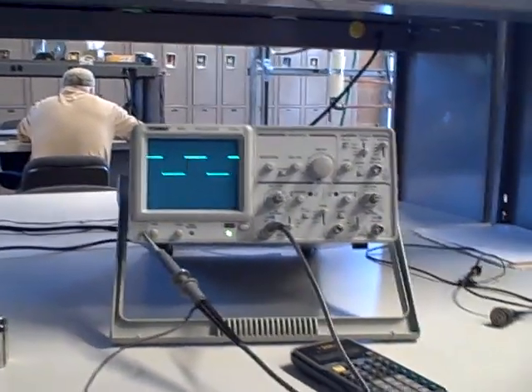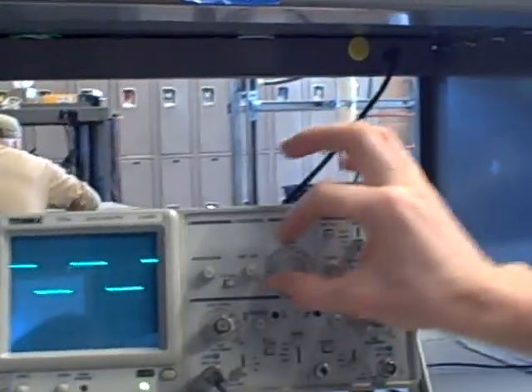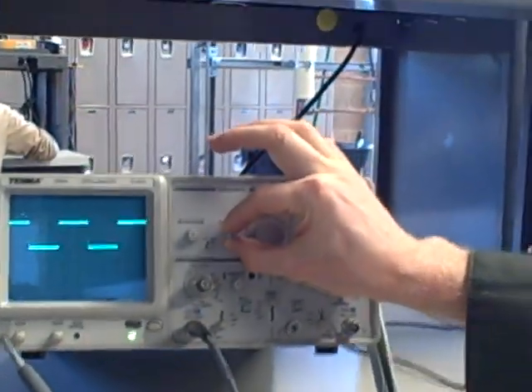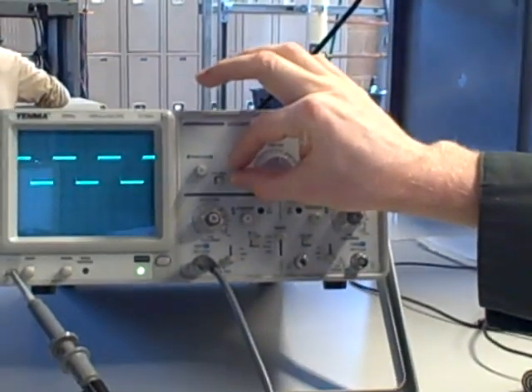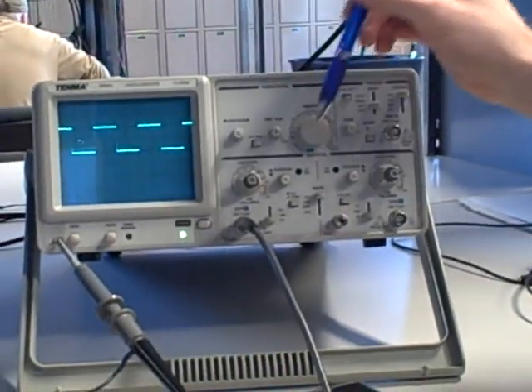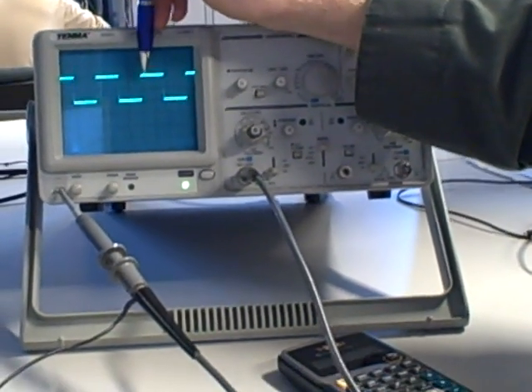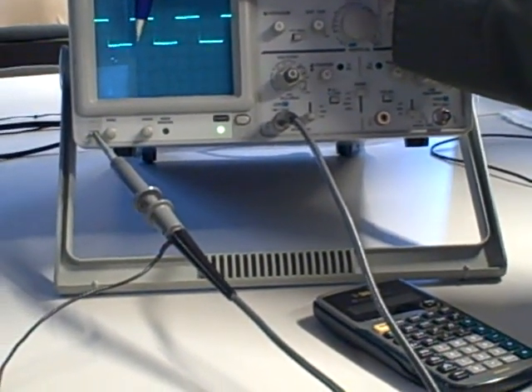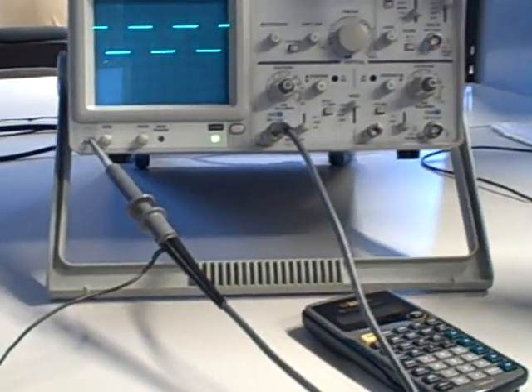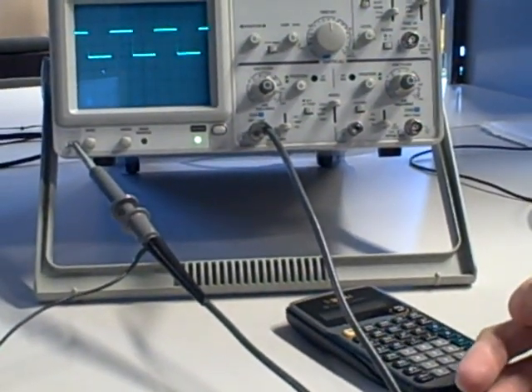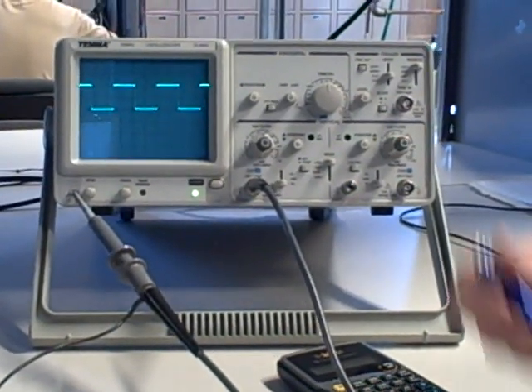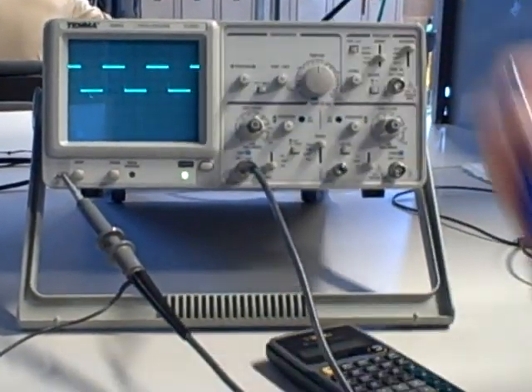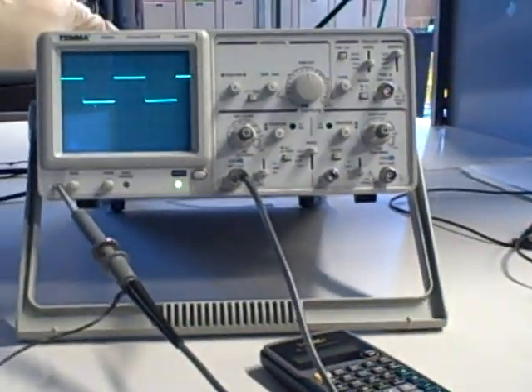In fact, I'll even prove that. I will take this sweep variable knob right here and move it off of calibration. And notice what happens. Now I can move it to any arbitrary point I want. If I were to try to calculate the time here, I would say, oh, one cycle takes one, two, three, about three and a half divisions. I'd try to work that out with my math, and I would falsely come to a higher frequency than 1,000 hertz until I realized, oh, no, this is actually off the calibrated position. I have to move it back, click, and now it's accurate.